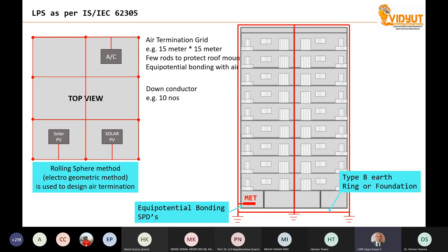So there is also some more science behind it. There is a lightning protection level and a risk assessment, which I am not going to explain. But in a simple building with a flat roof, you have to make a mesh at the top of the building. And if there are protruded items, such as roof-mounted electrical appliances, let us say solar PV and an air conditioner chiller unit, these protruded electrical appliances require additional protection, such as a rod. Within the angle, the rod protects against direct lightning strike on these electrical appliances.